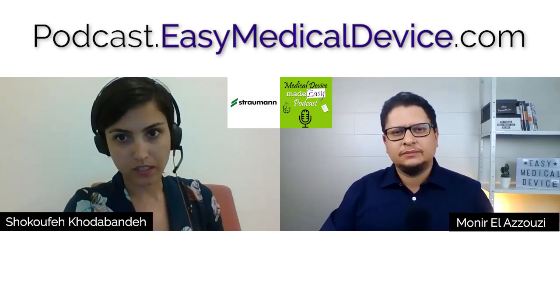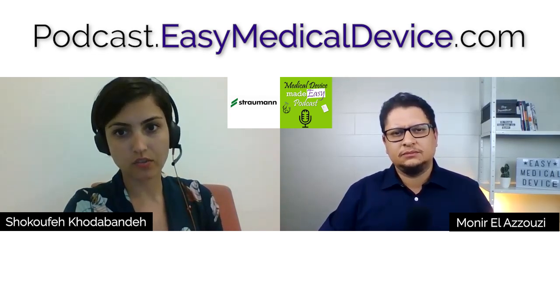Yes and yes. I mean, one of the biggest topics, coming back to communication with notified bodies, is that we had a lot of questions that mainly remained the same question marks throughout the first 1 or 2 years. It was only at the time of actual certification that we could get them finally answered. For example, one of the biggest discussions for the dental industry is the discussion of well-established technologies. Dental implants were under discussion whether or not they can be considered well-established technologies as screws are, and this has a huge impact on our industry.